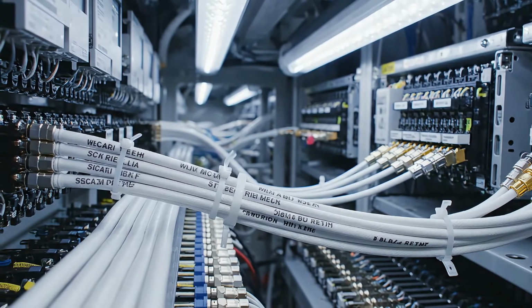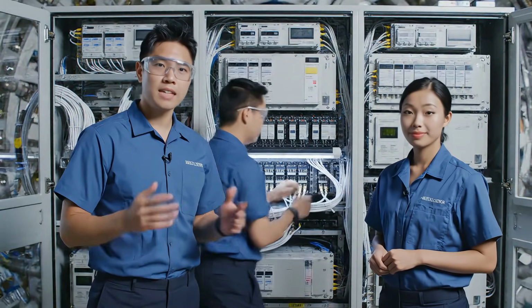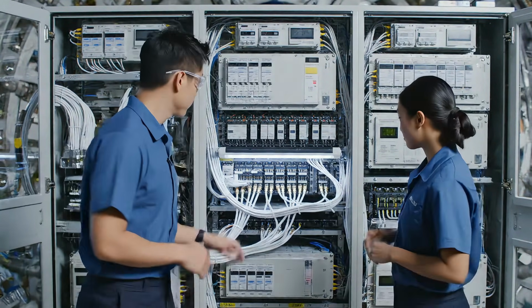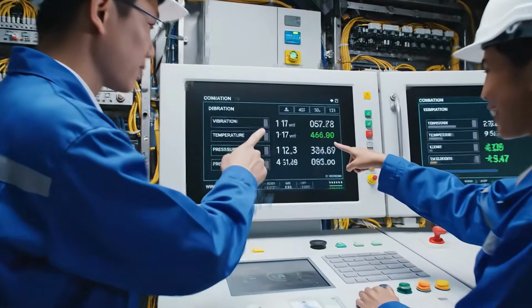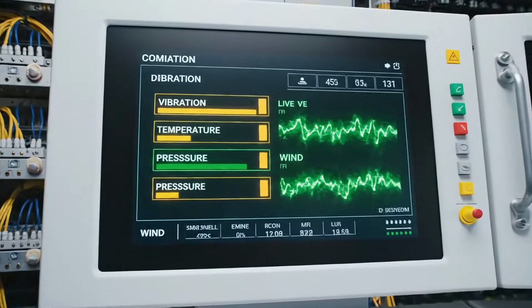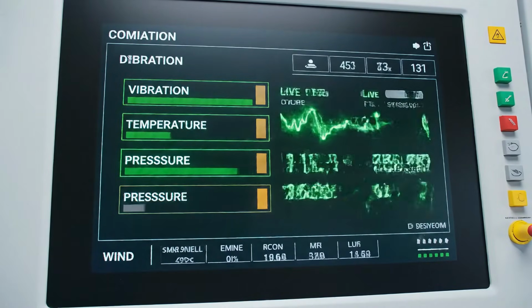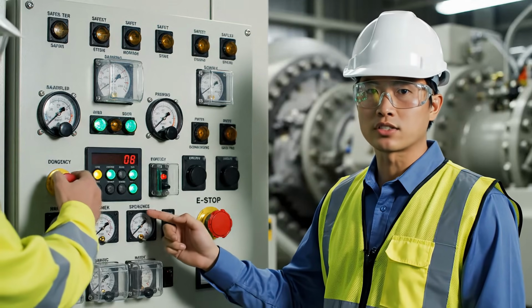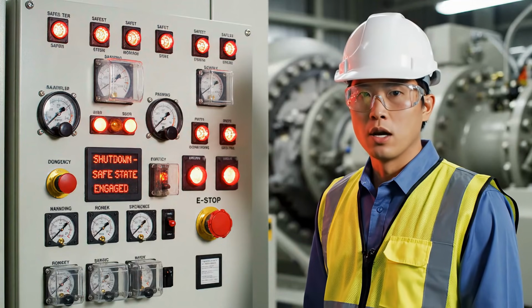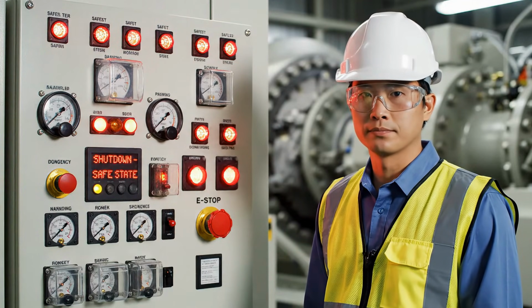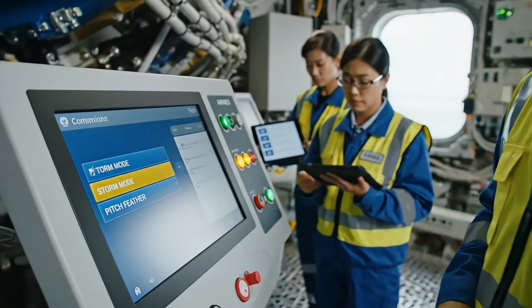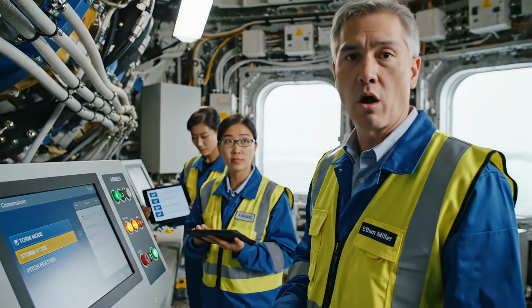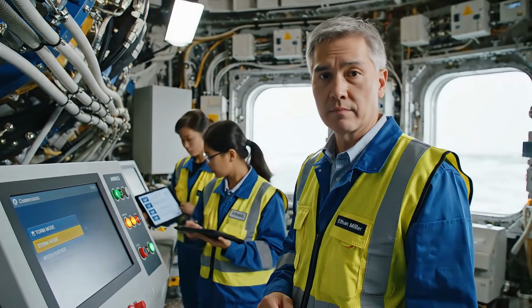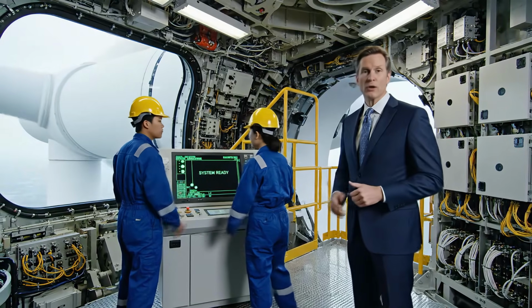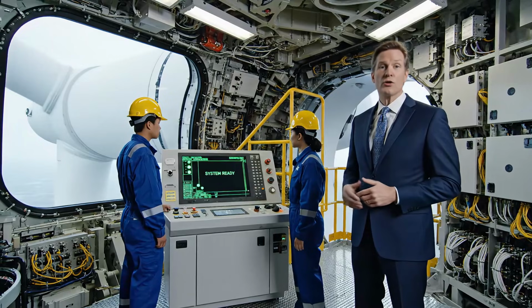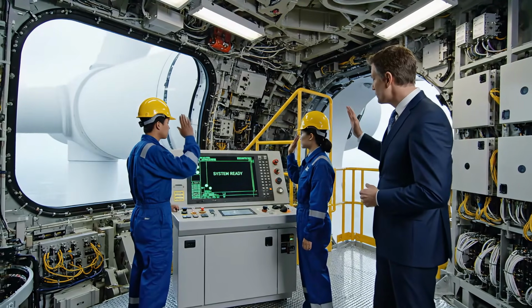Then we connect the nervous system, SCADA, sensors, and the networks that carry every decision. Commissioning is mapping. Every sensor must report the truth before control can act. We test the safety chain, interlocks, emergency stop, and protective modes, because fail-safe matters more than output. We arm storm behavior, because offshore wind can go from calm to violent in minutes. When power, control, and protection agree, the turbine is no longer a structure. It's a system ready to move.